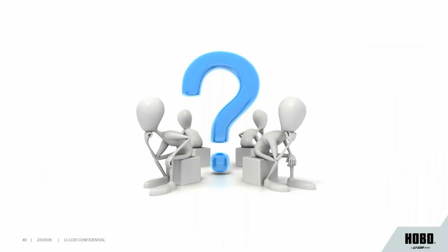So, yeah. Great. Another question that came in, Elizabeth, I'll hand this one over to you. What does the calibration protocol look like for marine versus freshwater? Are there different calibrations applicable to both? Yes, so we just use in air and in water. When we started testing the LI-192 back in the 1970s, I was not working for Licor at that time, but we did a lot of work and we determined that the marine and freshwater calibration could be the same. So there's no need to change that.